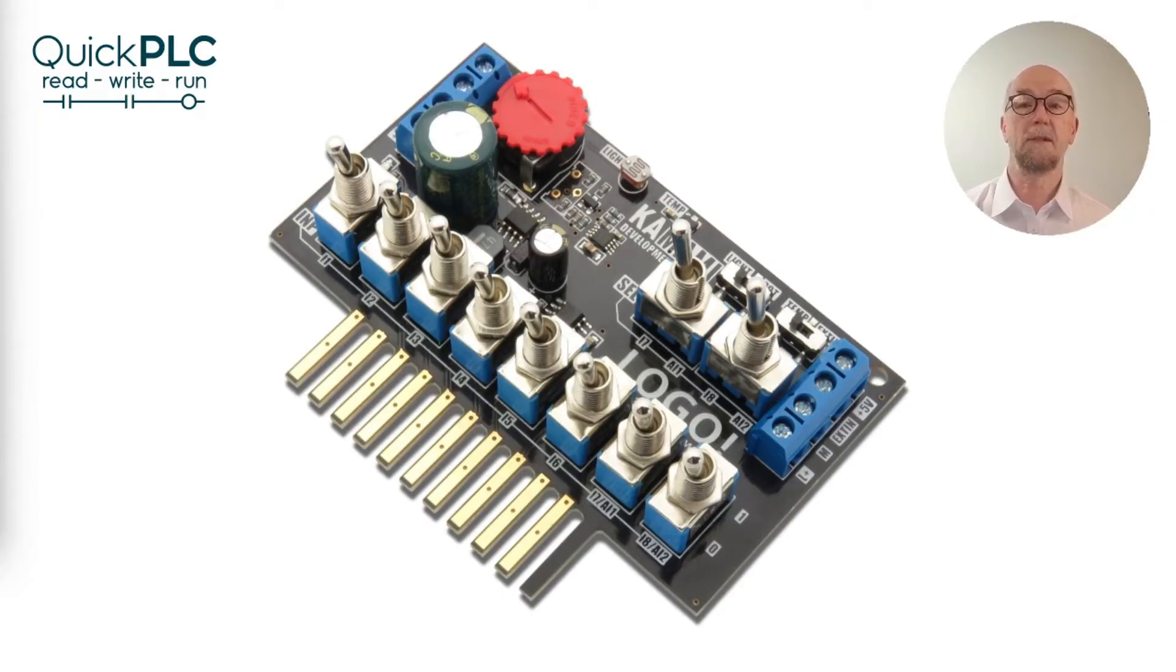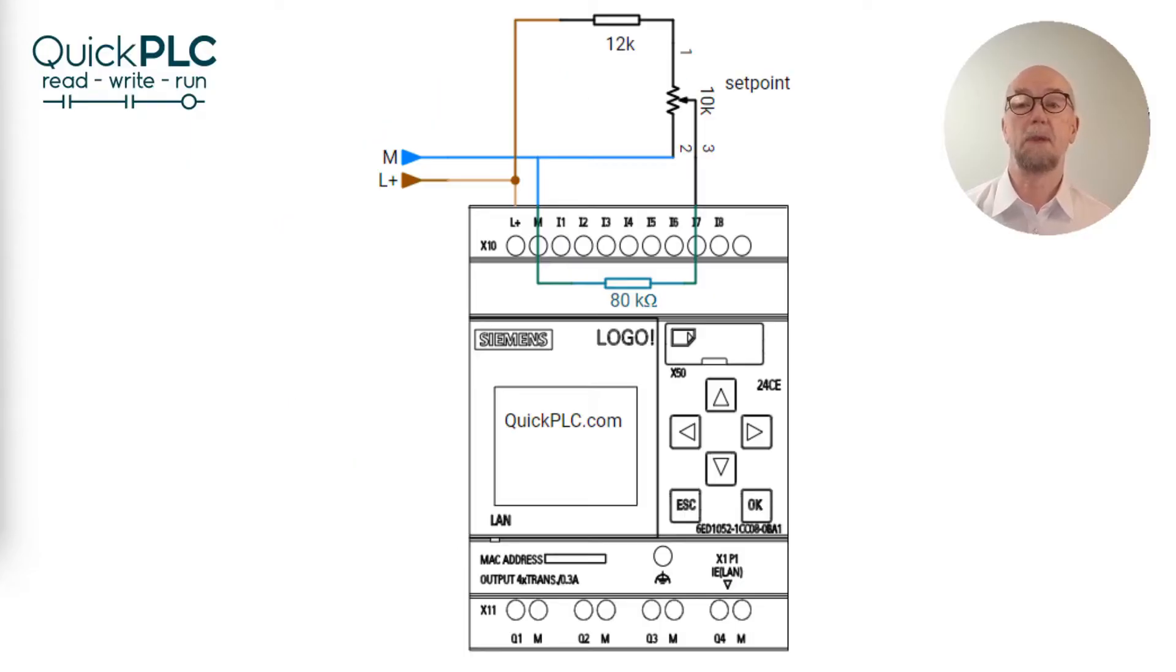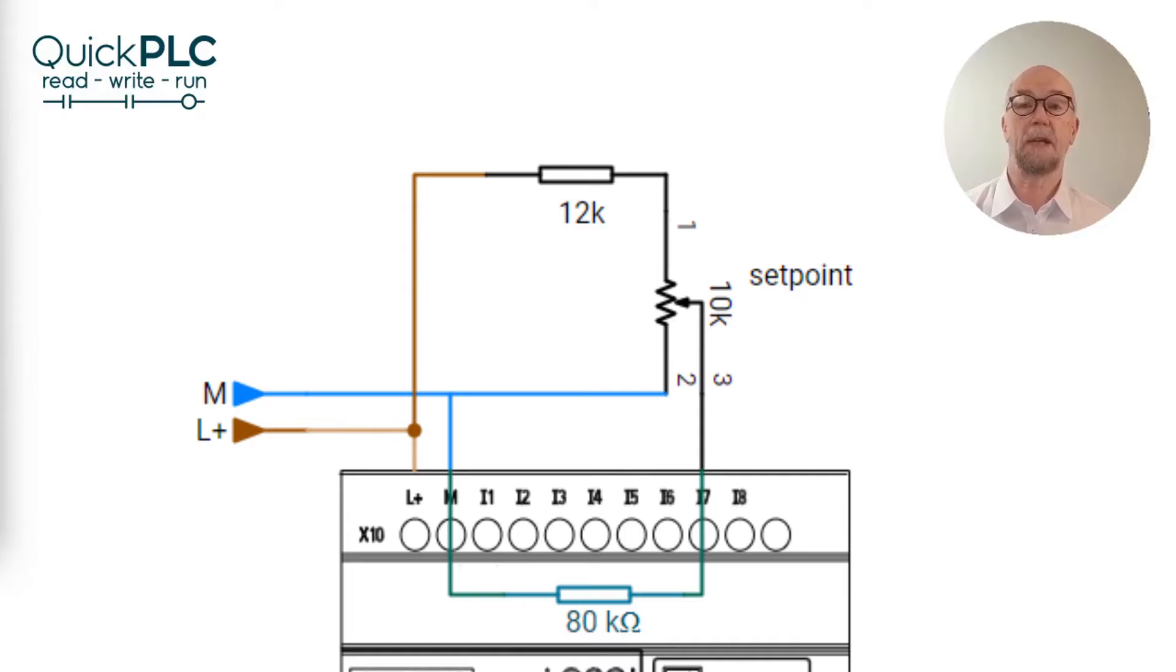A potentiometer can be used to drive the analog input. On the simulator, 10 volt supply is generated for the pot, but we can use the 24 volt supply if we add in a voltage dropping resistor in series. In this sample circuit, we're using a 10k potentiometer and we need 10 volts at the top terminal to get 1000 counts internally.